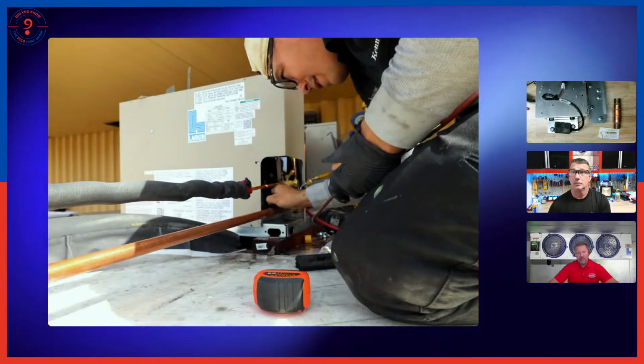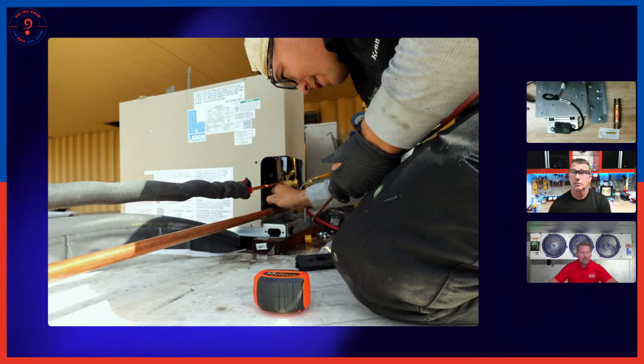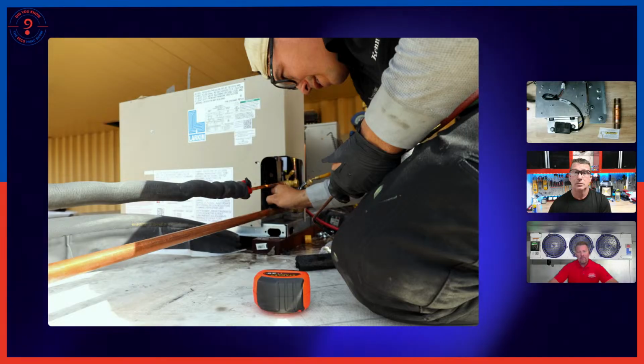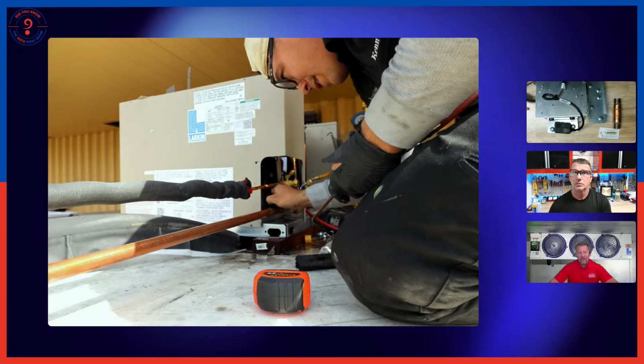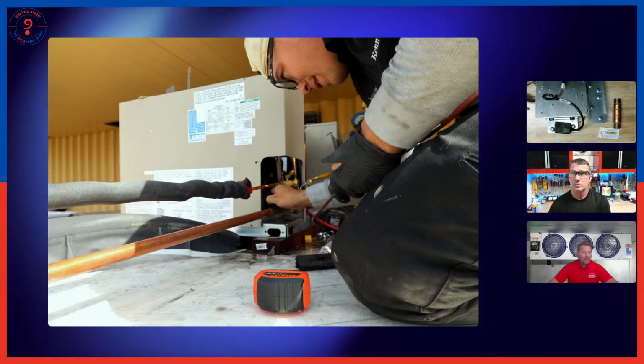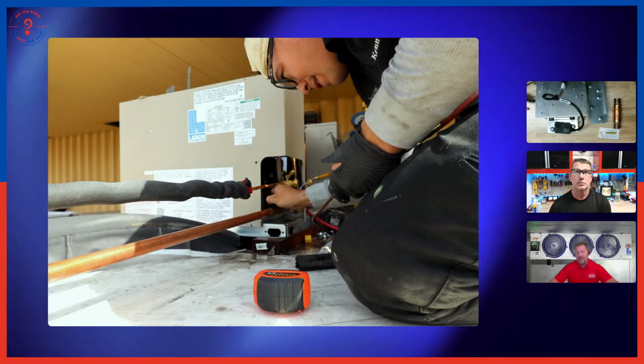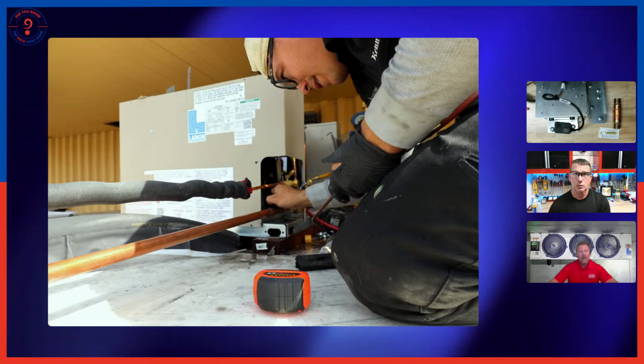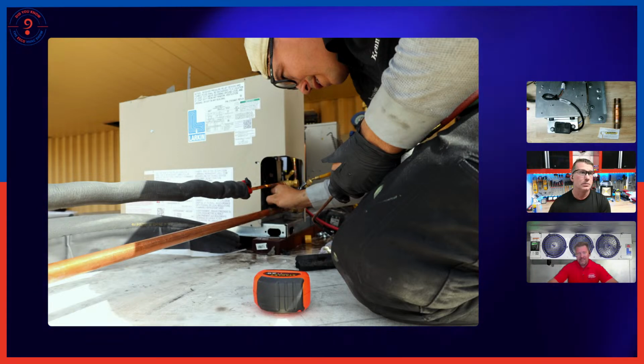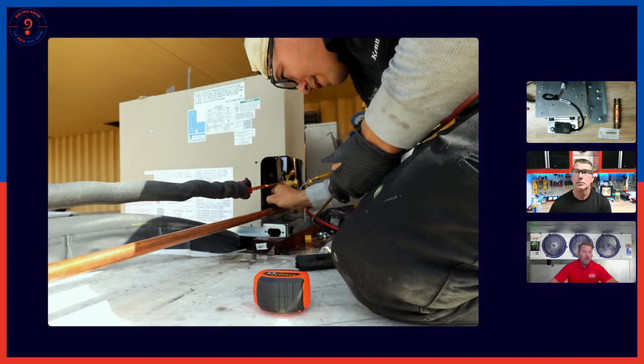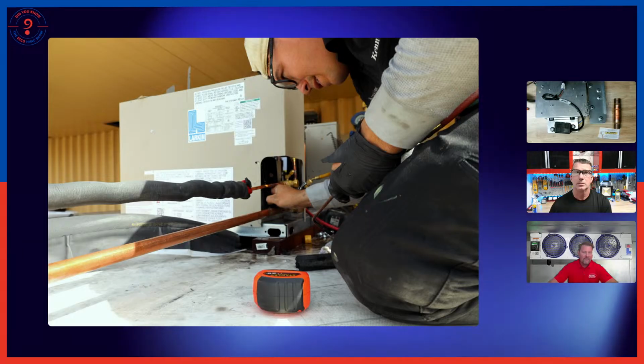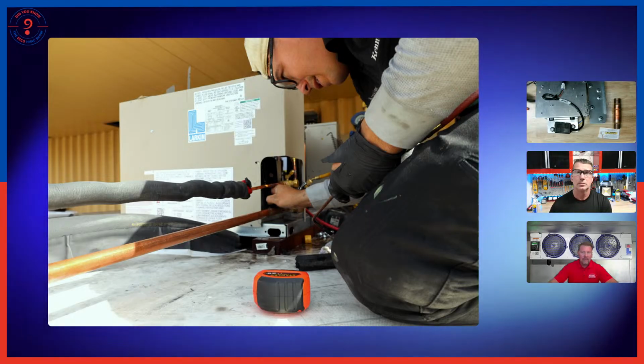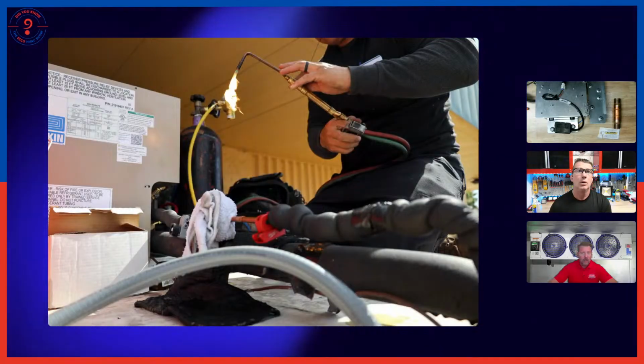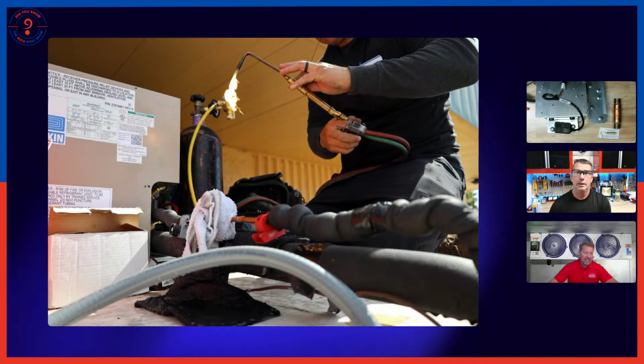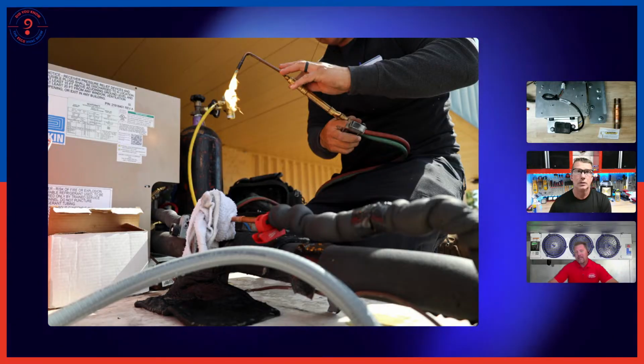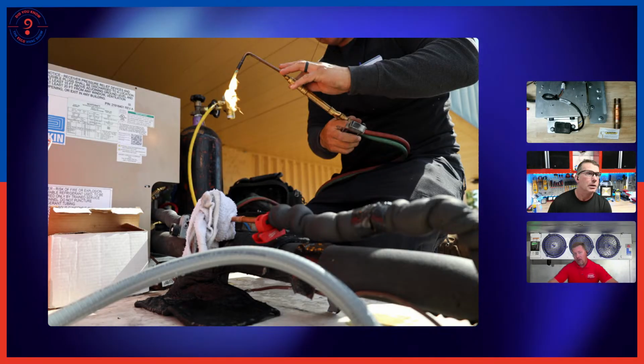Yep. Now, one thing that needs to be addressed with A2Ls, again, is our solenoid and our check valve, you'll see where we place them. In this instance, on that picture that you see there, this is the initial installation before A2Ls. Where we ended up putting the solenoid valve, because this was a short run, we ended up putting it just to the left of where the liquid line leaves the condensing unit in that picture. So about where his clamp is holding the insulation back. Yep. That's where we put the liquid line solenoid in this case, because it was a short run.